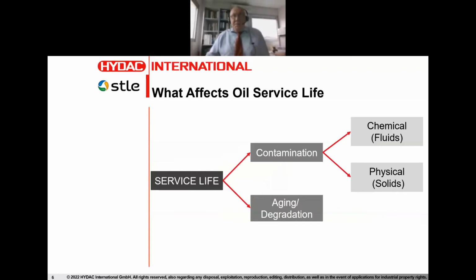So again, service life depends on oil service life, on contaminants, and let's say ingrained aging and degradation processes. Since the oil is already heated, the oil is exposed to atmosphere, particularly oxygen. If there are contaminants present, then obviously this degradation, or this depletion of service life, can be further accelerated.